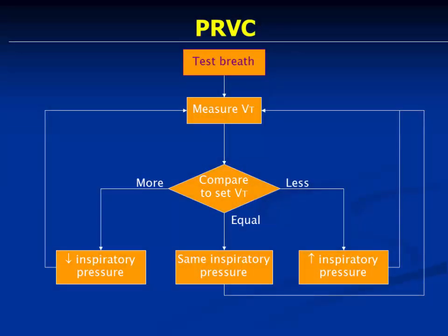So PRVC is doing a test breath, measuring tidal volume, and comparing it with the set tidal volume. If it is less, increase the inspiratory pressure. If it is more, decrease the inspiratory pressure. If same, it's okay.